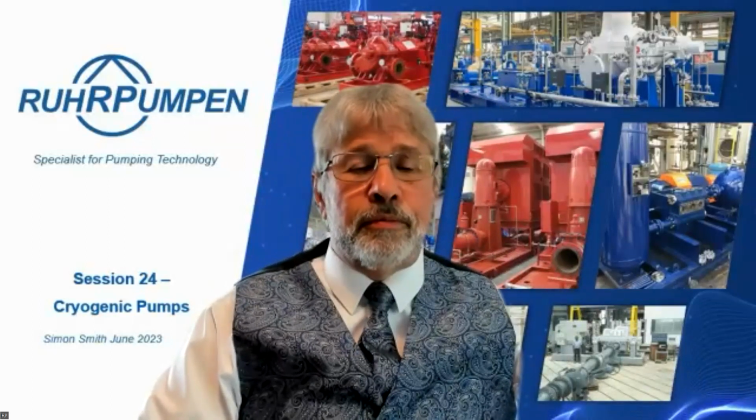Anonymous attendee, when should a VS6 pump with normal suction versus double suction be used? What are the disadvantages of double suction VS6 pumps? Are they then called a VS7? Well, yes, you're right. It becomes a VS7 when you have a double suction. They're not very common. The double suction first stage becomes very big in diameter, puts up the size of the suction barrel, and often you'll find that the advantage is not there. When you get to very, very big VS6, VS7 pumps, then a double suction, double volute design could work for you, but it's not very common. Almost always a single suction design.